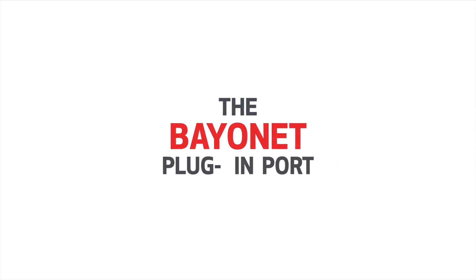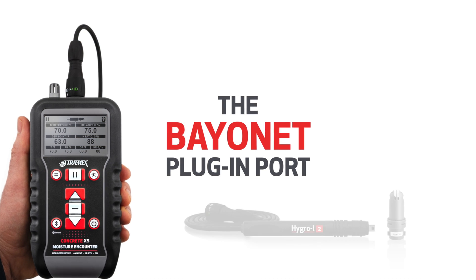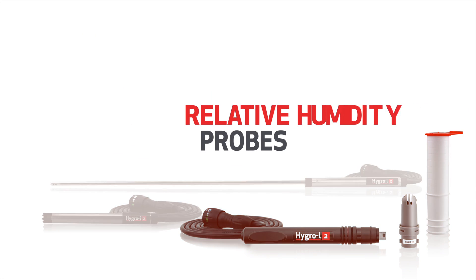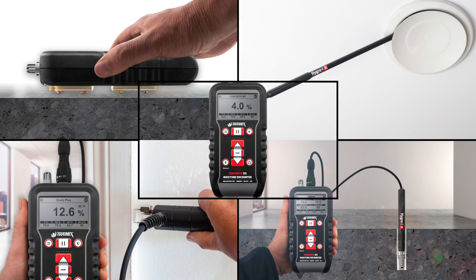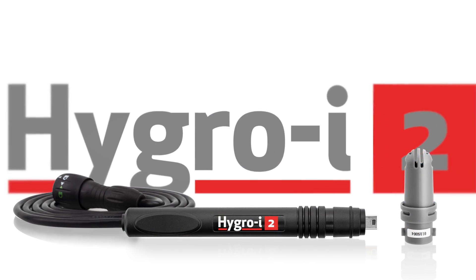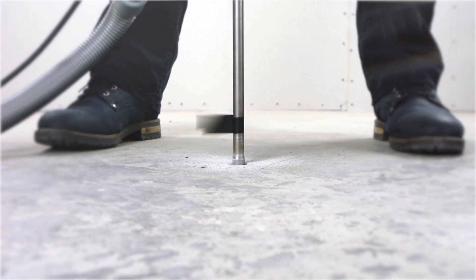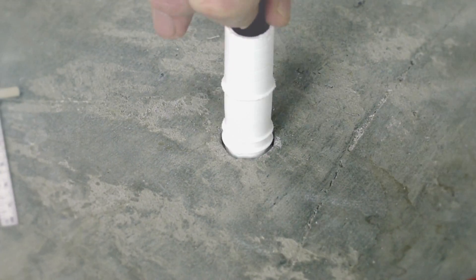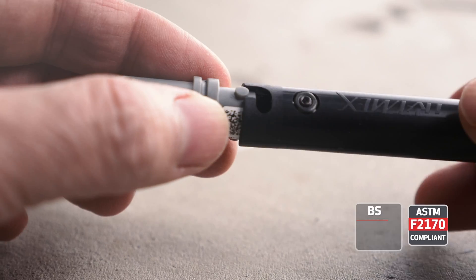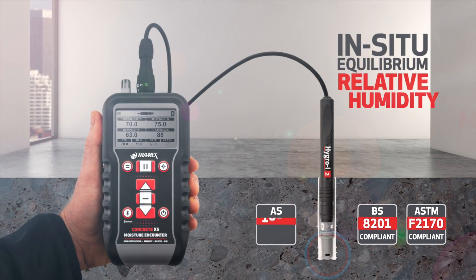The bayonet plug-in port allows for the use of optional probe accessories. A variety of Tramex relative humidity probes can be connected for ambient RH measurements within air spaces. Using the optional plug-in Hygro-i2 RH probes, a concrete slab can be tested with the in-situ equilibrium relative humidity method, as per international standards including ASTM F2170, BS 8201 and AS1884.